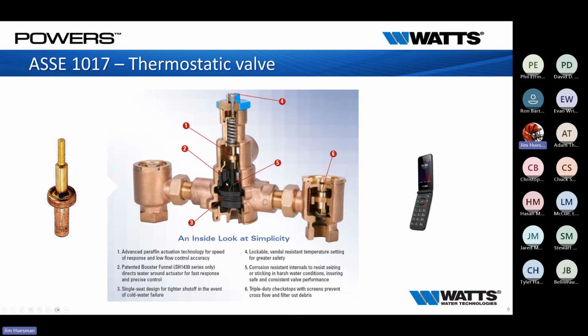Other features we have on these, if designed with those valves, are service checks built in. This allows you to shut it off, get in there and rebuild it. Also strainers - and if you've sat through any of my presentations, I don't care what piece of equipment we're talking about, I always stress the strainers. Keep the garbage out of my valve and this valve will operate for years upon years. Dump a bunch of sediment and debris in here and it won't work. So strainers are a big one for me. I'm always pushing strainers - keep all that garbage, debris, and things floating around in the system out of the valve you may have just spent $2,000 on. Just one simple screen will really save that.